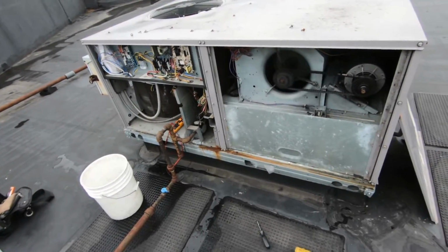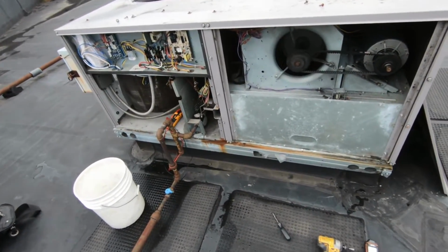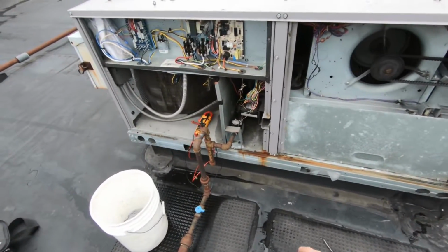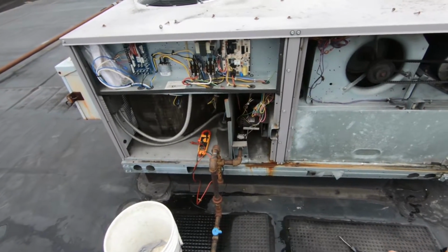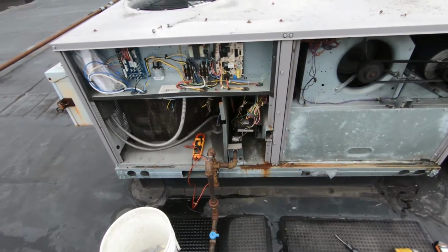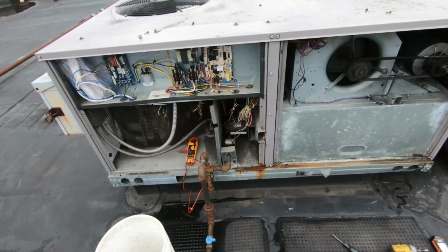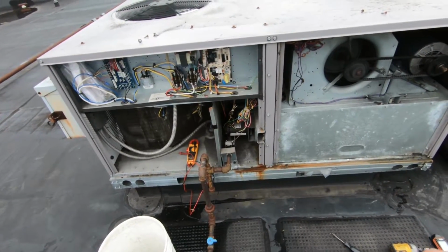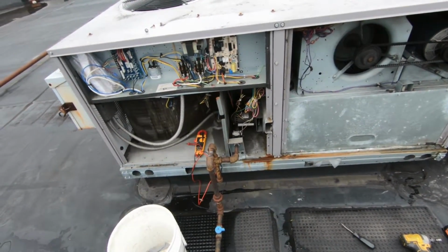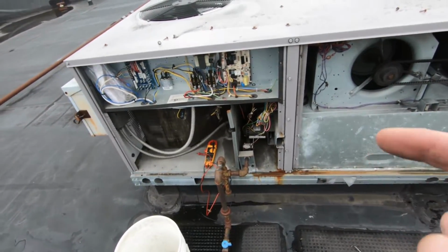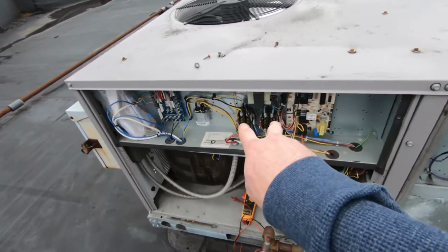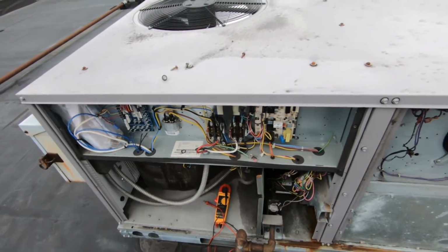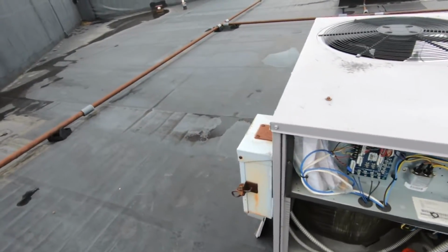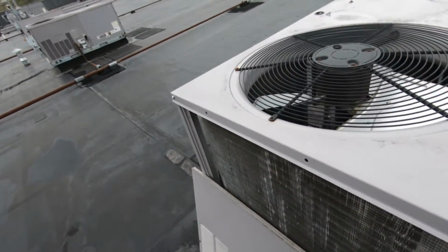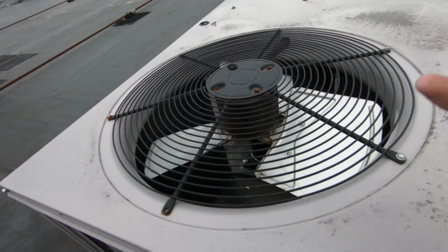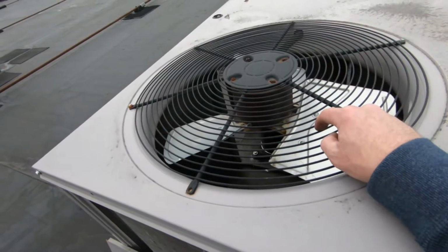All right, so we're gonna need a belt, filters, heat exchanger, all heating parts that we normally write up when we do a heat exchanger. That's burners, flame sensor, igniter, combustion blower. I will kick this on heat just to make sure that the gas valve's working. We'll also write up a new ignition control board. It's gonna need a couple new contactors because they're burnt and pitted. The condenser fan motor, the shaft has a lot of slop in it, and there's a lot of grease dripping out of the bottom of it. So we're gonna go ahead and replace that as well.